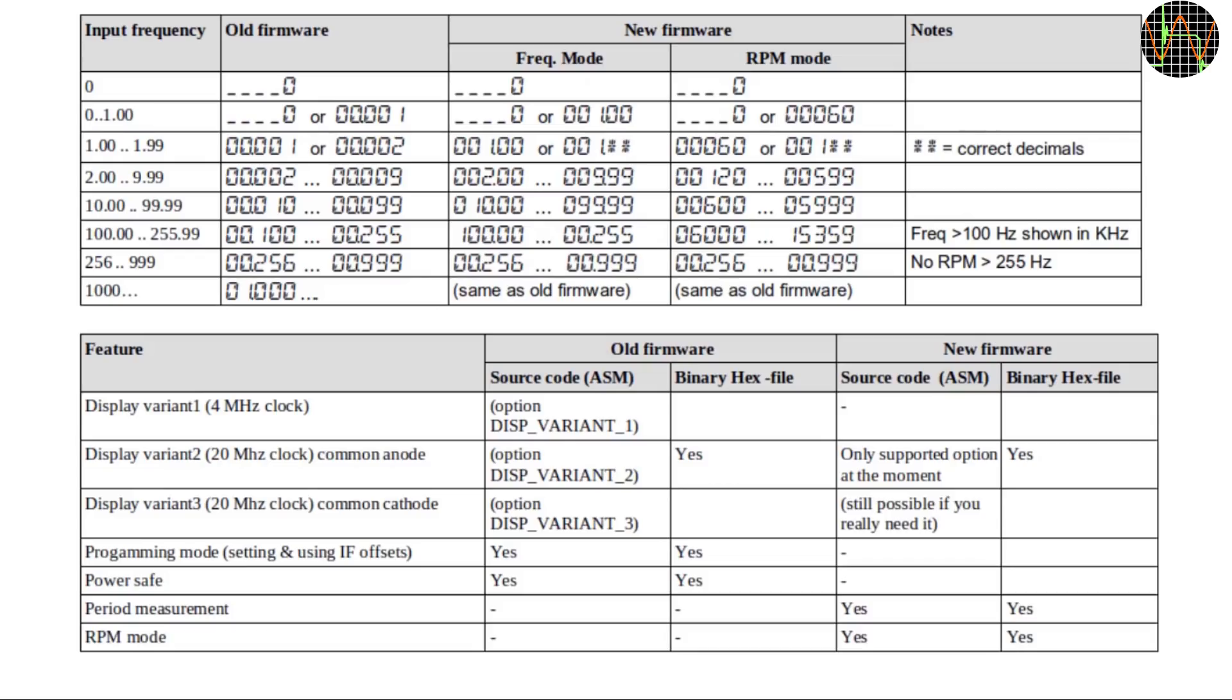Last not least, I want to show these two tables. The first one shows how the old firmware and the new firmware behave for frequencies from 0 to 256 Hz. For anything above 256, the two firmware versions behave the same. I just want to point out that frequencies will switch from the old format for frequencies above 100 and RPM will simply switch to frequency display above 15359 RPM. It will automatically switch back to RPM if the frequency falls back into the RPM range.